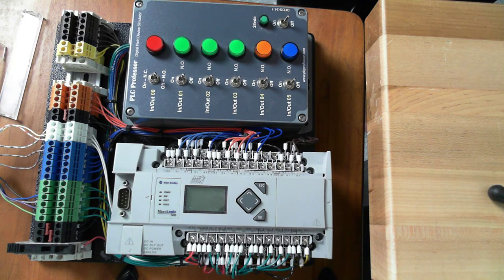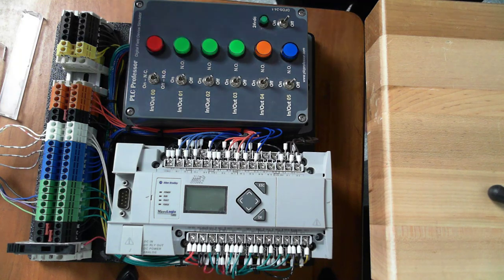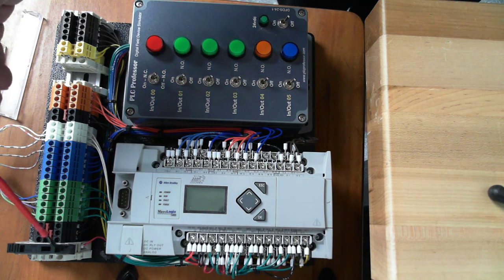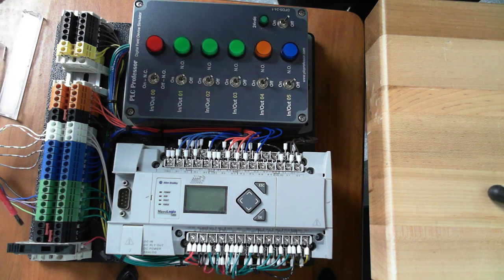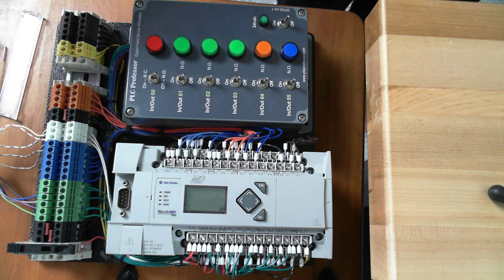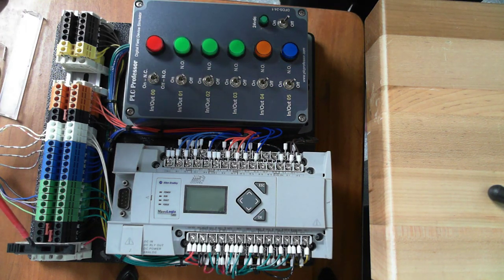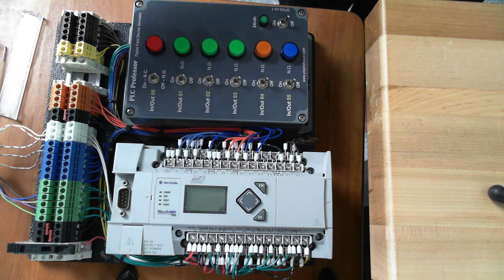And then of course for plus DC, we do extend it out to this switched fused terminal block, but we have nothing connected on the other side. So if we have circuitry out here, devices that need plus 24 volts DC, we can get it out through this fused switched terminal block. That gives us the ability to turn all this out here on or off.